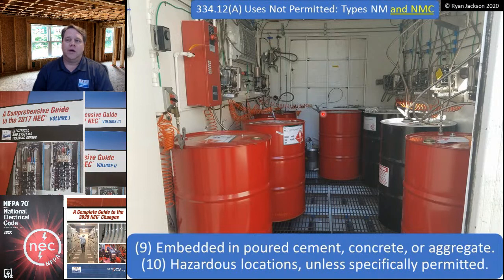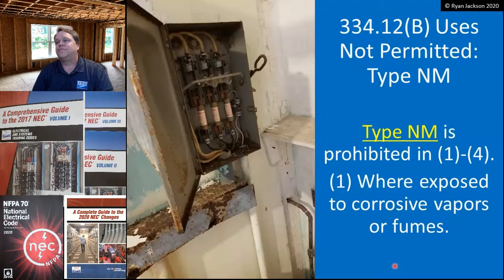Yeah, you're not going to use NM cable in there. Although it does say hazardous locations unless specifically permitted. Is it ever specifically permitted? Yes. Article 504 for intrinsic safety says you can use any wiring method you want. So as bizarre as it would be, if you want to use Romex for intrinsically safe wiring, be my guest. Probably not going to happen.